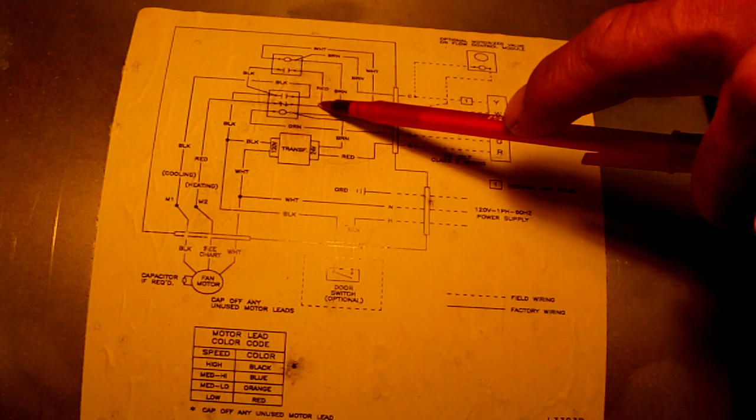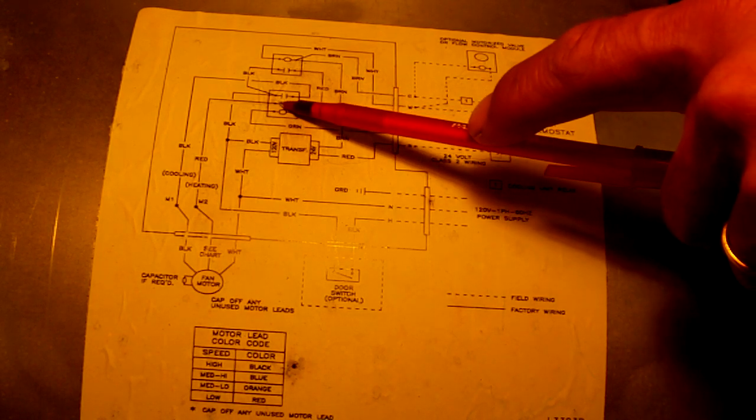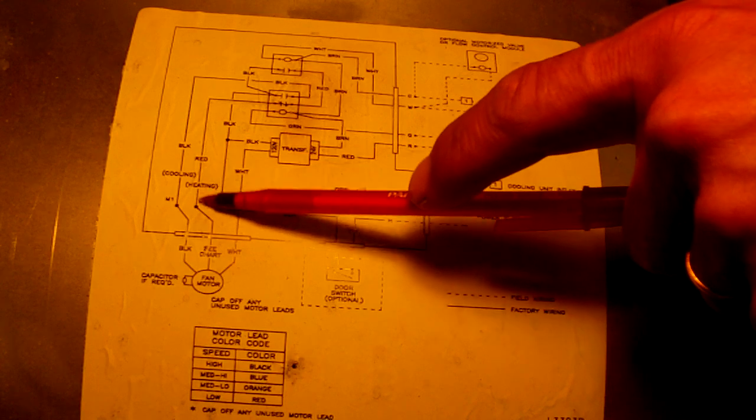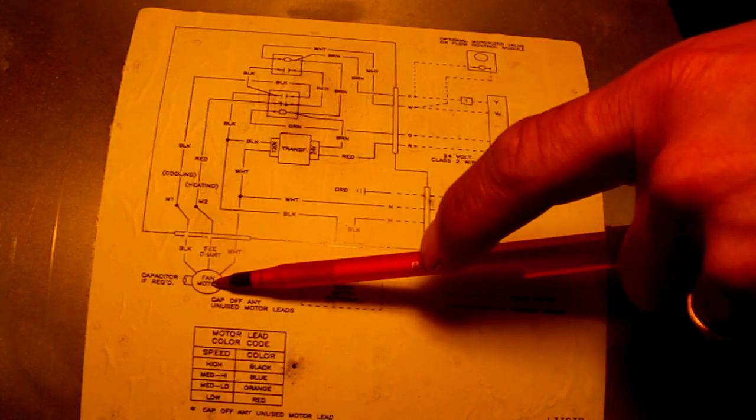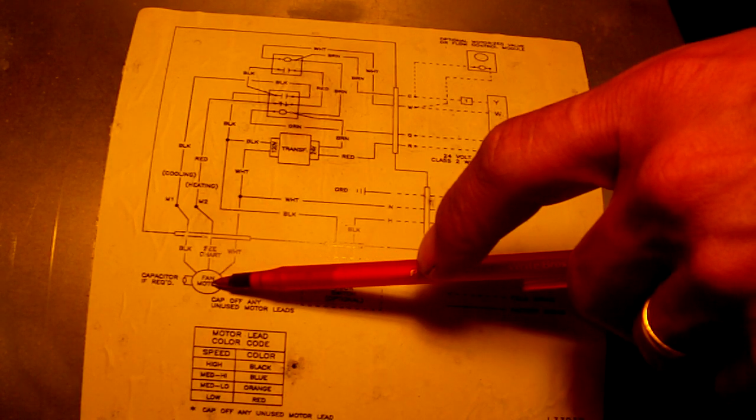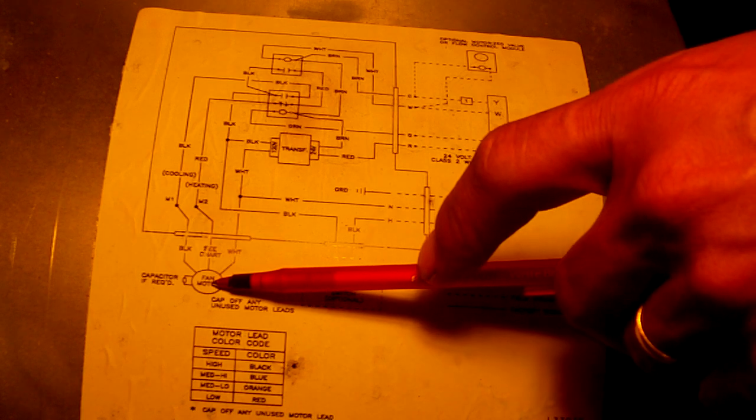It heats up, the heat sequencer pops and closes this contact, sending L1 through here, through this relay, goes down here, and boom - right away the blower will start kicking.